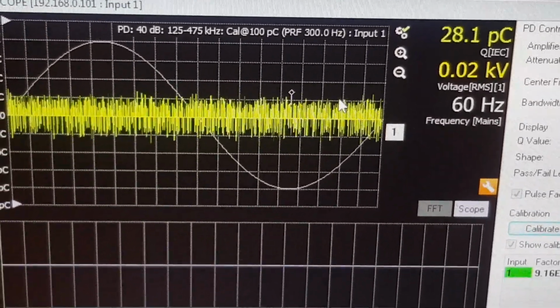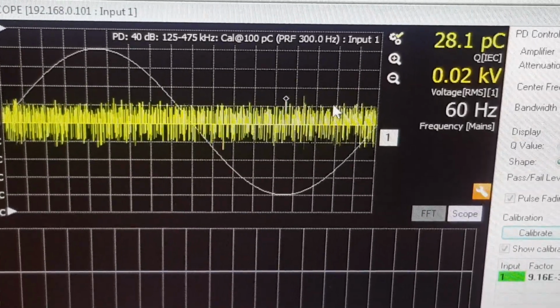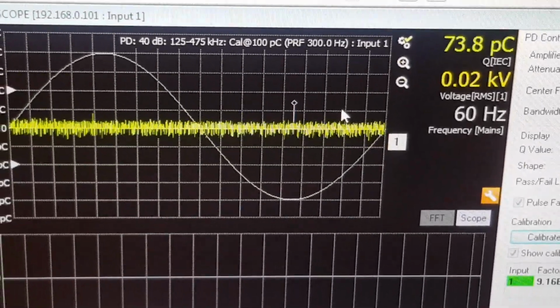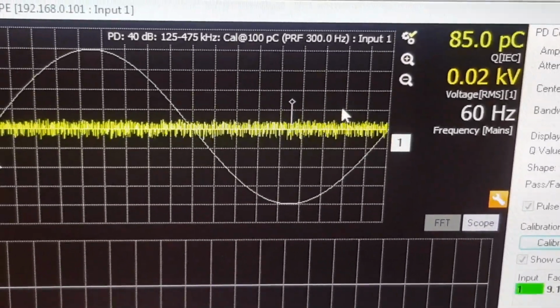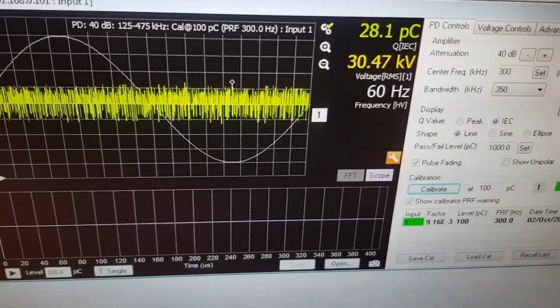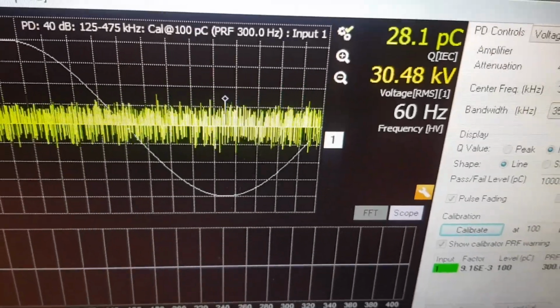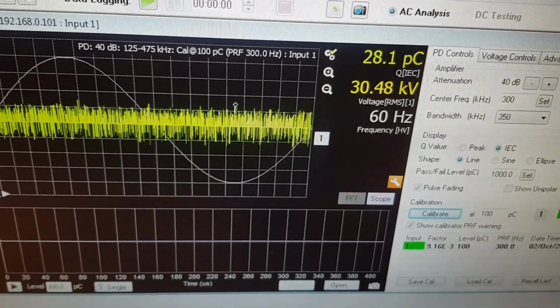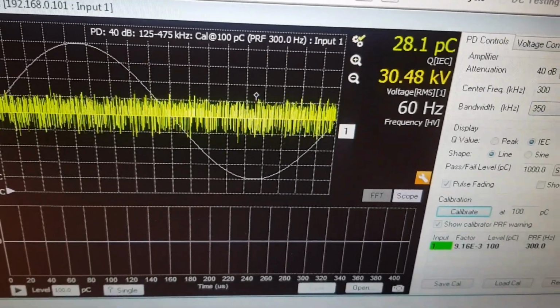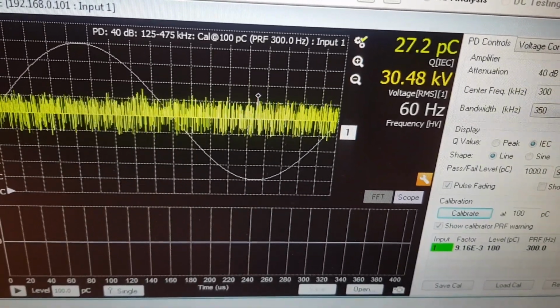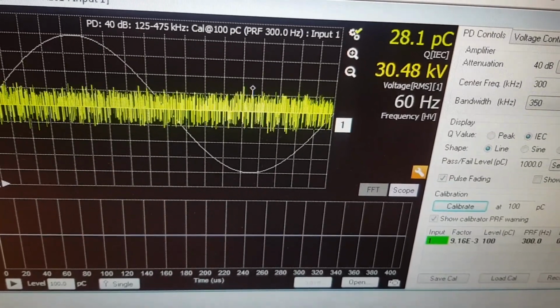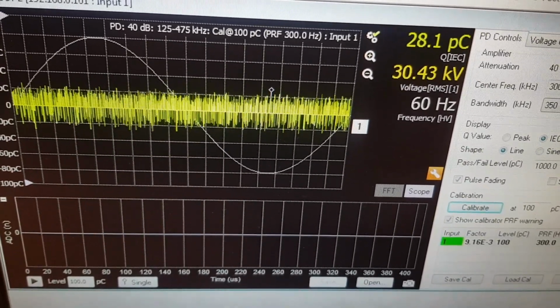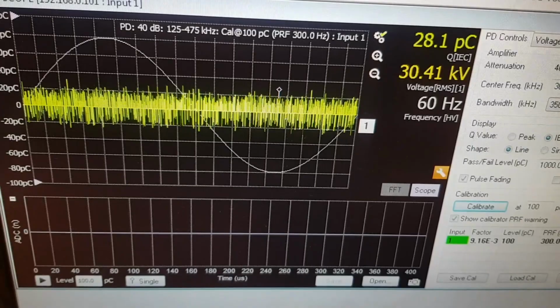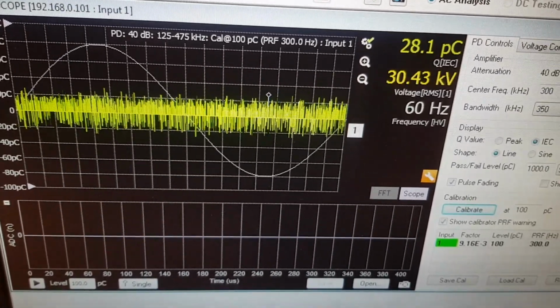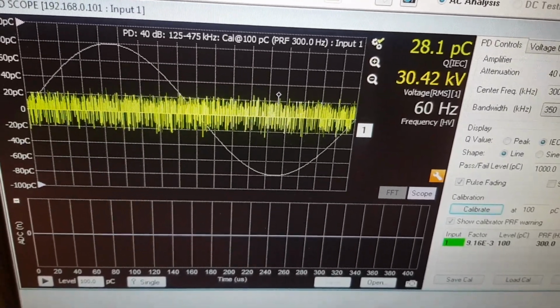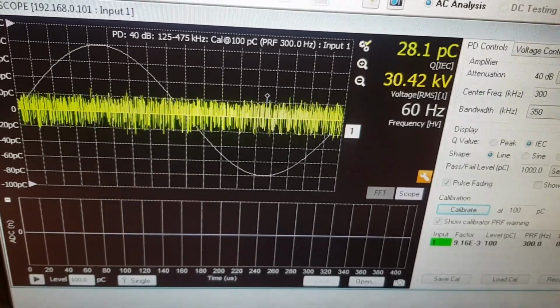Now we will energize these two discs at 30 kilovolt and we'll see that there is no PD coming. Now this is the PD detector at 30 kilovolt applied to these two discs of insulators, and as you can see here, the PD level is still around 30 picocoulomb, which is the same as the background noise. So at this voltage level, the two healthy insulators don't produce any type of partial discharge.